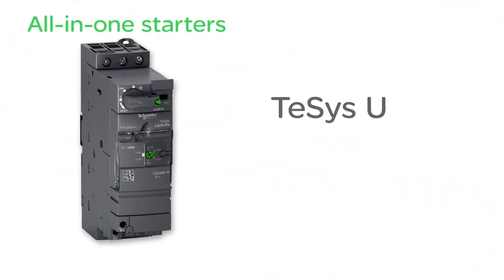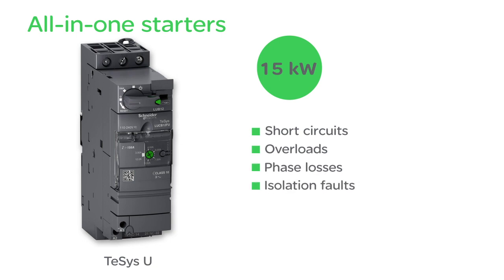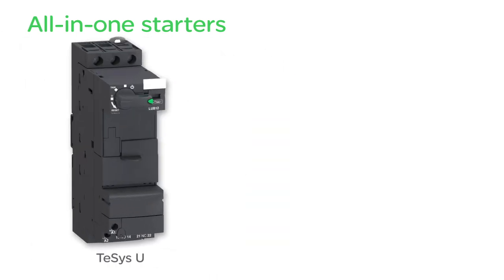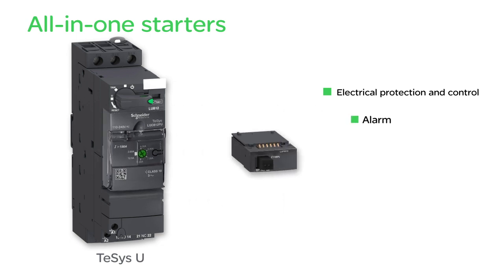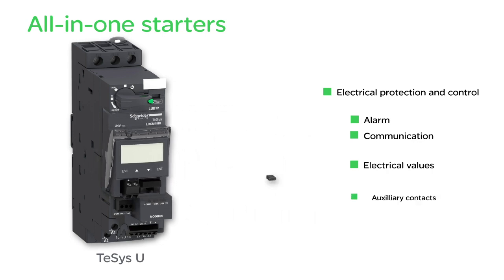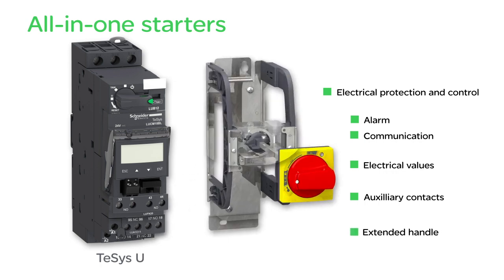TeSys U starters are suitable for three-phase motors up to 15 kilowatts. They protect against short circuits, overloads, phase loss, and insulation defects. They allow direct on-off control or reverse control with two directions of rotation. Modules fit into the TeSys U base block to enable the following functions: protection and control, alarm, communication, and display of electrical values. Auxiliary contacts can also be added, as well as an extended handle.